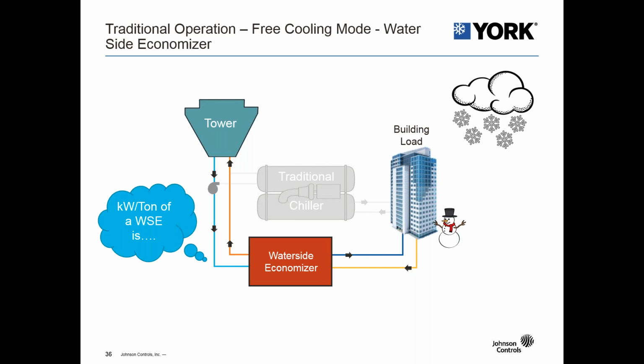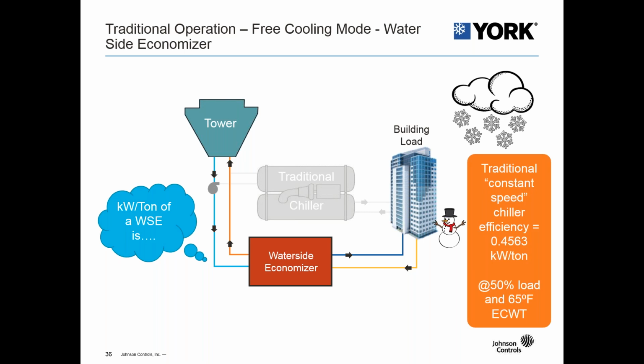But what is the kW per ton of a water side economizer? For this example, we'll just assume that it's free. Since we call it free cooling, that's what we'll refer to it as. And the reason a lot of people thought, or it was always referred to as free, was because to run a traditional chiller with constant speed prior to having variable speed drives when water side economizers were widely used, the chiller efficiency was a 0.45 kW per ton at 50% load, and the chillers were limited to a 65 degrees entering condenser water temperature. They weren't able to operate below that. So there were significant savings when looking at water side economizers with many operating hours with low tower water.